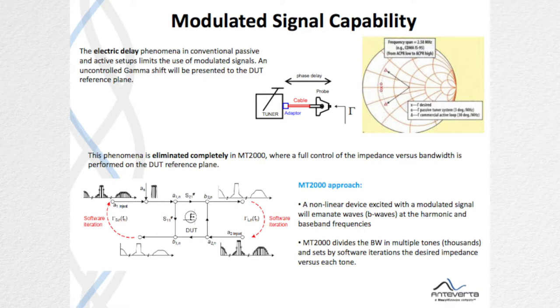Now, in the MT2000 active load pull system, we use a relatively simple approach to basically control the gamma versus frequency within the modulation bandwidth. If you look at this diagram, whenever in a measurement system you have a realistic modulated signal, that's going to be a finite sequence in the time domain. So your signal is going to be periodic. Just to give an example, a wideband CDMA signal according to standard will have about 11,000 tones within a modulation bandwidth that are closely spaced apart by about 1.5 kilohertz.